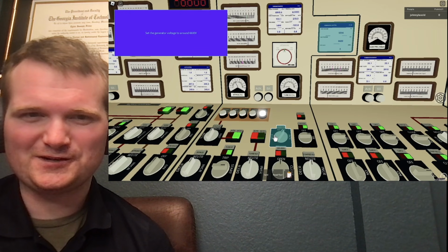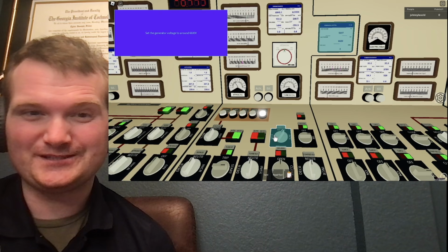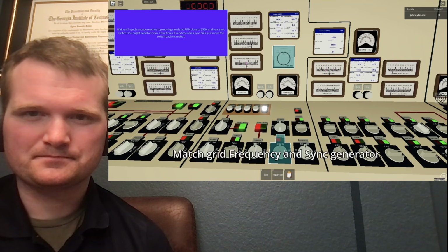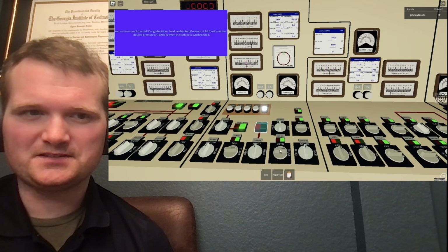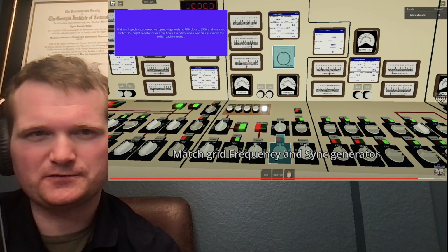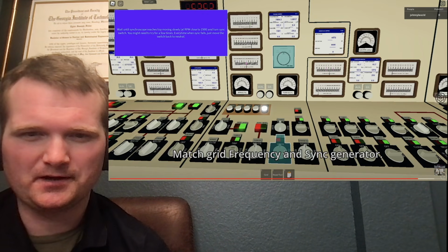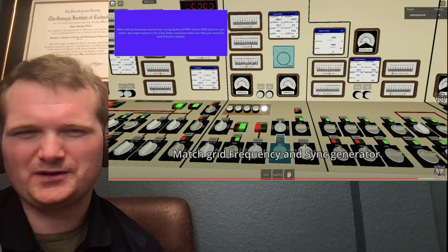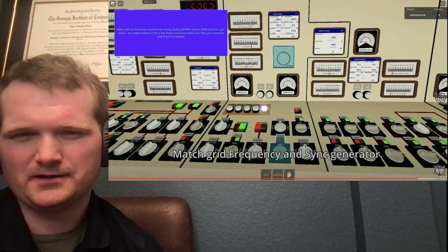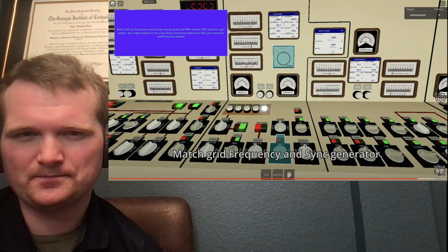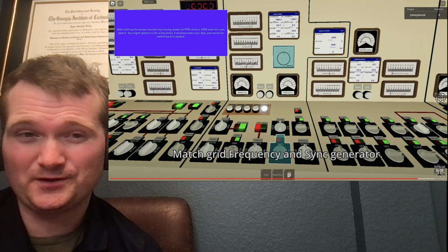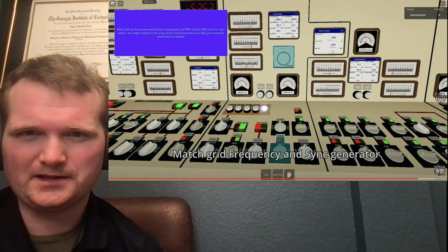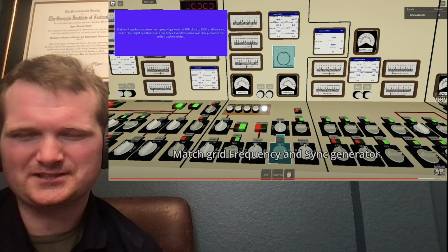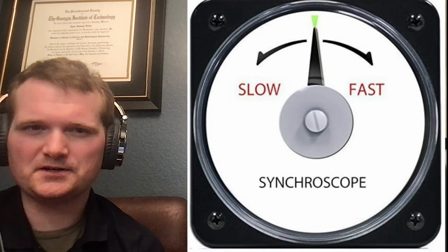Yeah, you're not going to hear plant sounds in the control room, or if you do, it's probably not a good thing. All right, now we're getting ready to sync. Match grid frequency and sync generator. You're actually going to want to go a little more, so that you're going to pick up a teeny tiny bit of the grid. And the reason for that is you really don't want the alternative where you lag the grid. Now this synchroscope is kind of hard to read, so here's a bigger one.